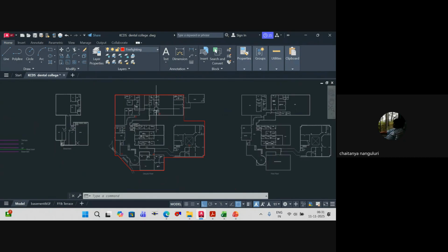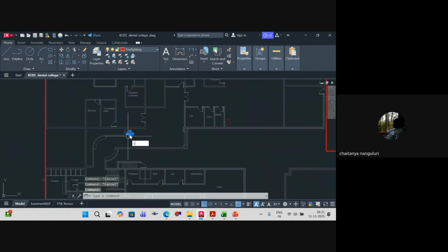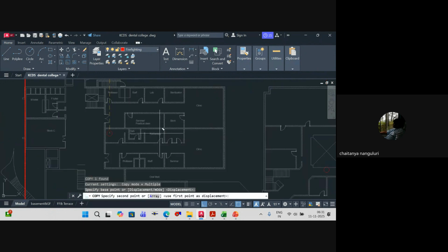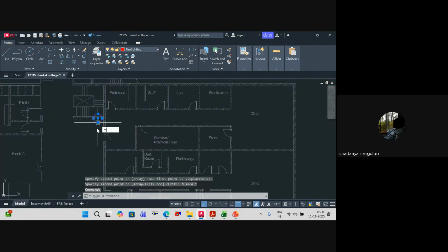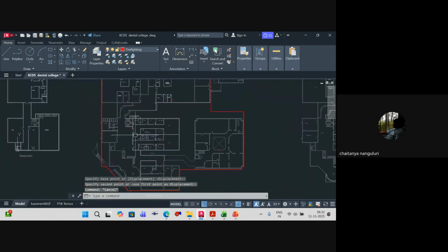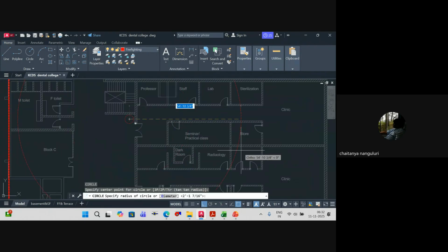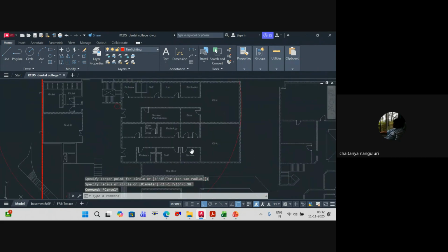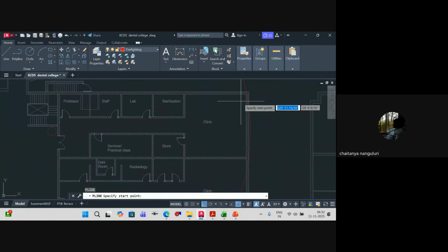So now how many are there? Basically 1, 2, 3, 4, 5 others. Of course, in this area we didn't do it, so we have to consider this one also. Here I'll place one near the staircase. I'll place one within 30 meters. See, 30 meters, right? That's 98 feet. So here I might require one more. Let's see. From here, if I want to do it, it's simple.